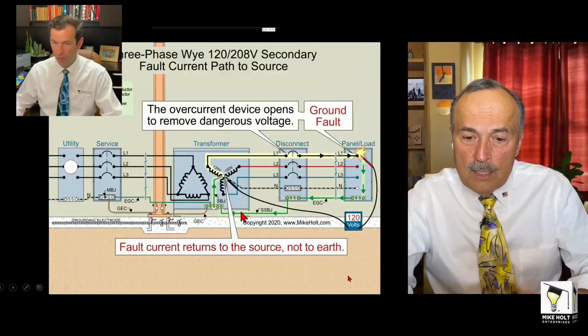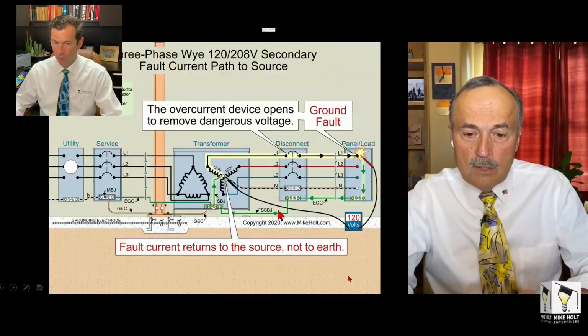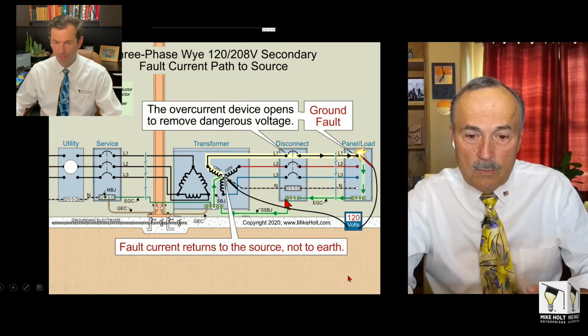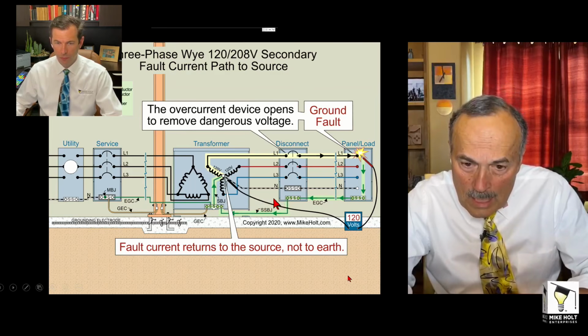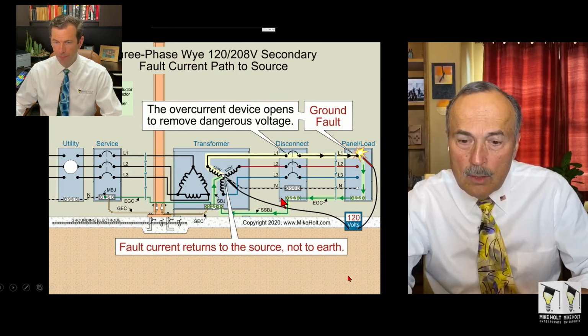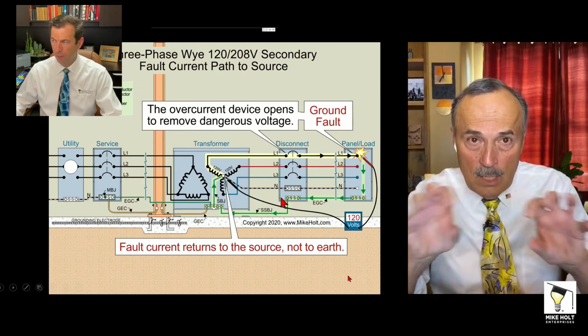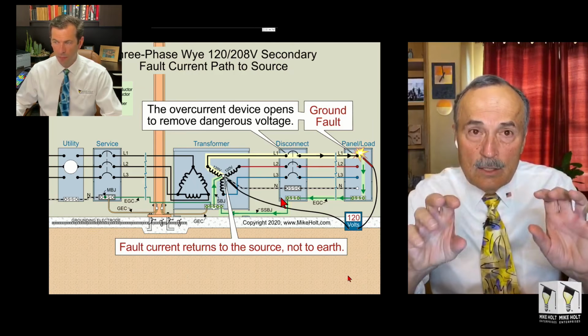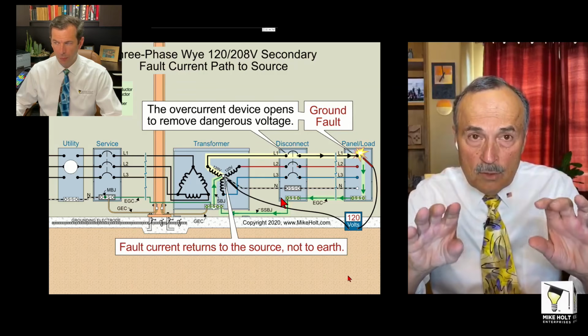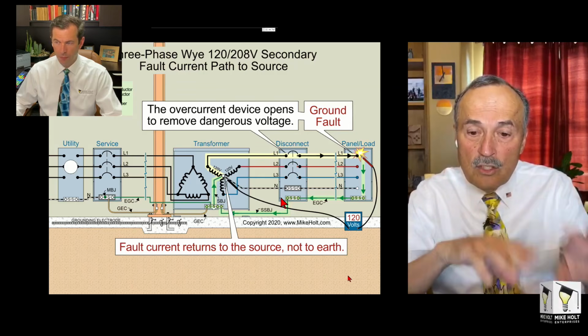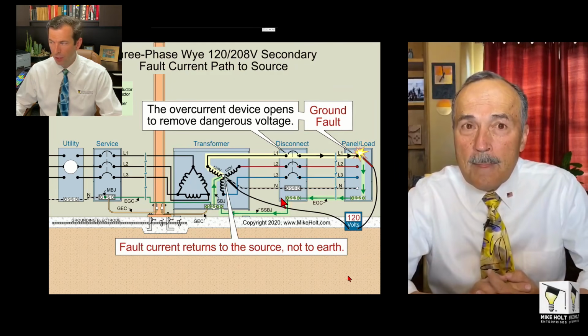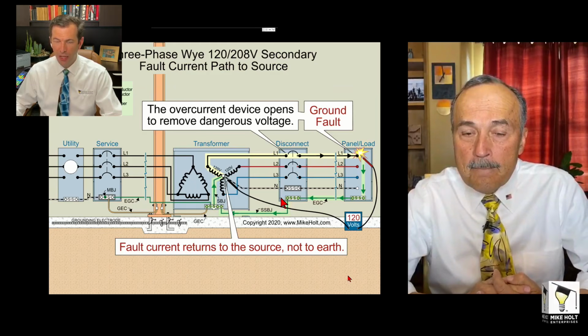Let's assume I physically don't install a system bonding jumper, a supply side bonding jumper here, right, Brian? Yep. You with me? I'm going to put a metal conduit between those two. Yep. With metal couplings, metal lock nuts. Okay, that is my supply side bonding jumper. So they just said you're running a metal conduit between the transformer and the disconnect. Okay, go ahead. Does the ground conductor have to bond to the conduit?